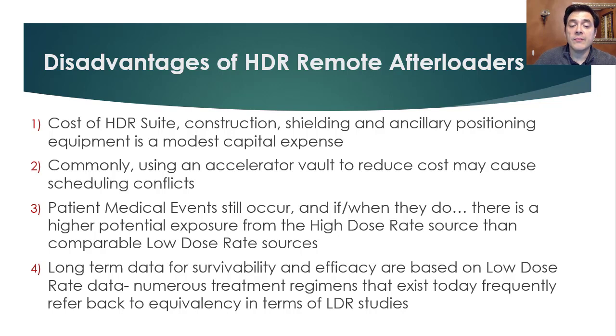Number three, patient medical events still do occur, such as the misplacement of a source or the loss of a source, although much less frequently. And if they do, there is a higher potential exposure from this high dose rate source than any comparable low dose rate source.